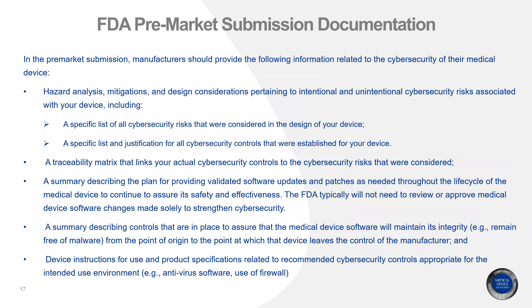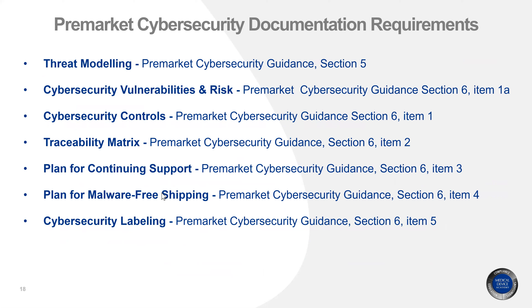For pre-market submission documentation, manufacturers should always establish, document, and maintain an ongoing process for identifying hazards associated with the cybersecurity of the device, evaluate and control the risk, and monitor the effectiveness of controls. FDA is aware that all cybersecurity risks cannot be anticipated — it is impossible. For that reason, FDA recommends all manufacturers document the process to assess cybersecurity risk as much as possible. The pre-market cybersecurity documentation requirements are: threat modeling, cybersecurity vulnerabilities and risk, cybersecurity controls, traceability matrix, plan for continuing support, plan for malware-free shipping, and cybersecurity labeling.